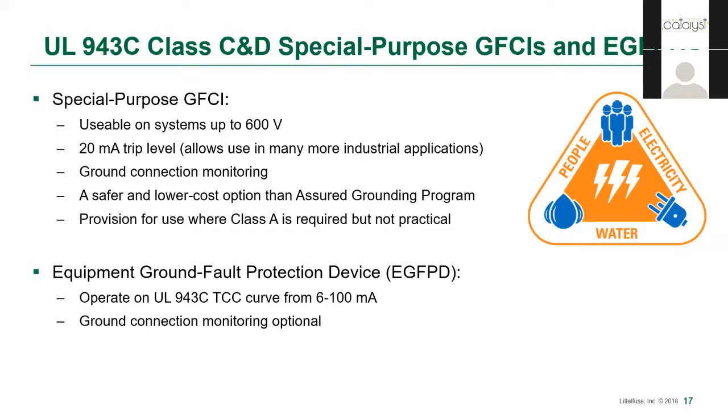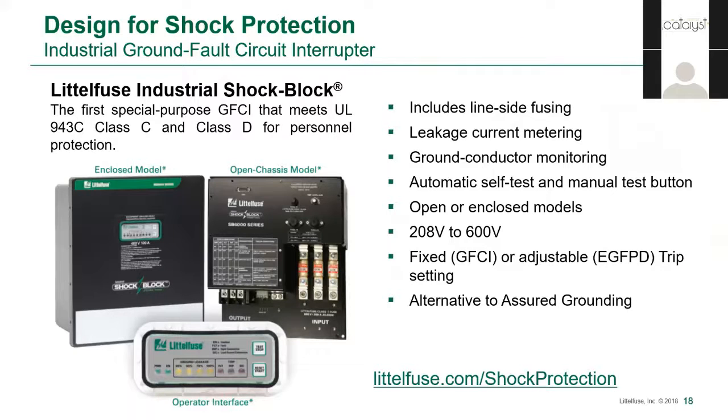The other type of device is an equipment ground fault protection device, with the acronym EGFPD. That name makes it clear that it is not personnel protection, because it allows adjustment of the trip level up to 100 milliamps, although it operates at the same UL 943 time-current curve as GFCIs. Here are some examples of special purpose GFCIs and EGFPD devices available on the market today. Going back to the hierarchy, a special purpose GFCI provides a safer substitute for the Assured Grounding Program and an engineering control that reduces the risk of shock. Make sure you check the standards that the products are tested to — the term GFCI isn't protected, so even if a product calls itself a GFCI and the marketing shows the UL 943 trip curve, it may not pass UL 943C.